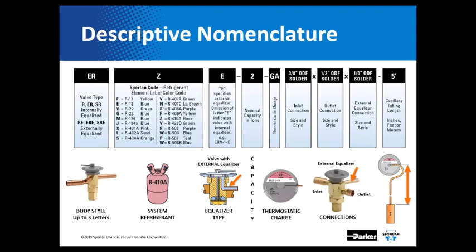This is a snapshot of our nomenclature — you can see it is all segmented and we're going to talk about all of these individually today. The first portion of our nomenclature is the valve type, also referred to as the body type; this could be one up to three letters long. The second segment is our refrigerant code — all the common refrigerants have a letter of the alphabet associated to them, and different colors as well. Following that is the equalizer: if there is an E present, that means it is externally equalized; without an E, that means it's internally equalized.